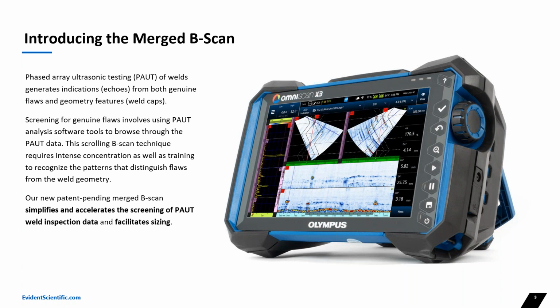So the merge B-scan is available with the OmniScan X3 series phase array equipment using the MXU 5.13 software revision and up. The same applies with the PC analysis software OmniPC. So you need either MXU or OmniPC 5.13 or higher to use the merge B-scan function. I will actually use a lot of OmniPC with existing data files for my demonstrations today.